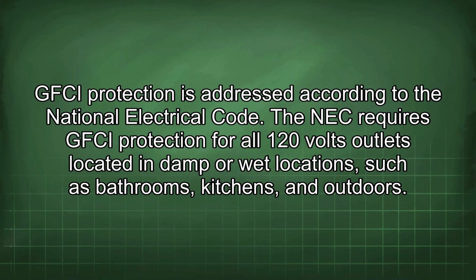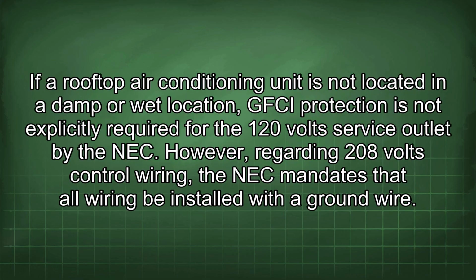GFCI protection is addressed according to the National Electrical Code. The NEC requires GFCI protection for all 120 volts outlets located in damp or wet locations such as bathrooms, kitchens, and outdoors. If a rooftop air conditioning unit is not located in a damp or wet location, GFCI protection is not explicitly required for the 120 volt service outlet by the NEC.